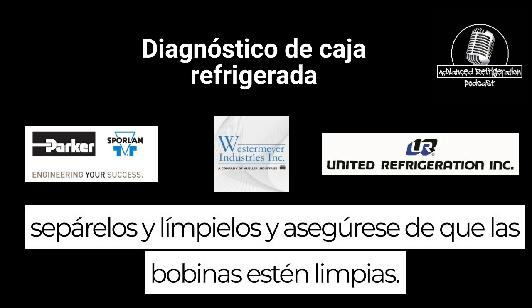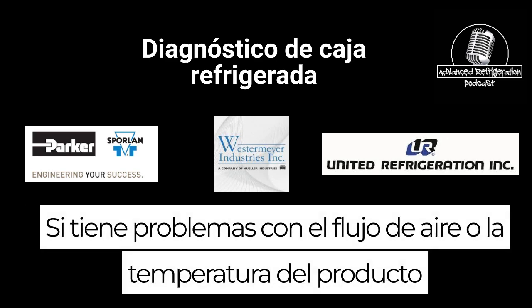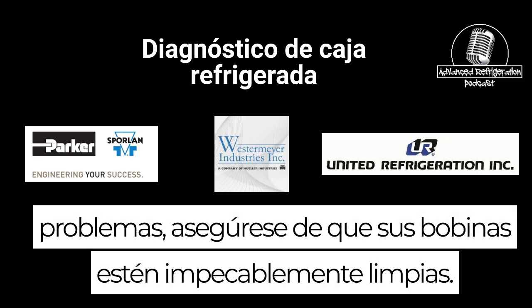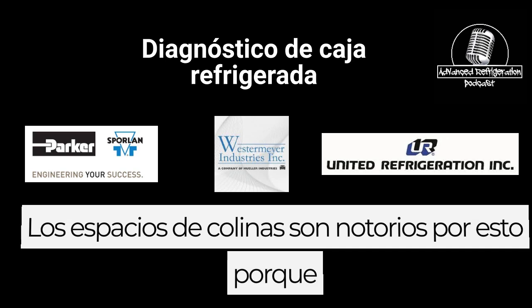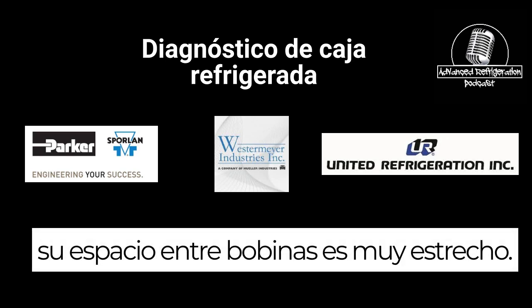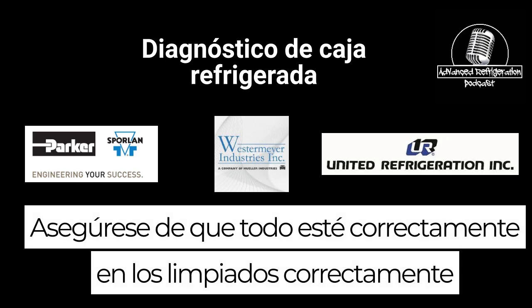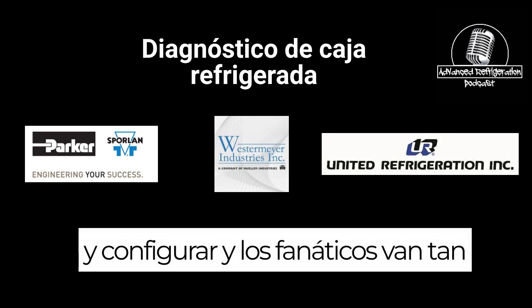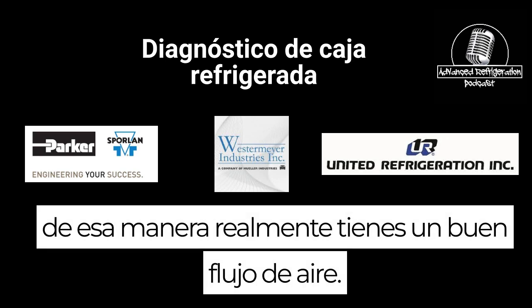Make sure the coils are clean. If you're having airflow issues or product temp issues, make sure your coils are spotless clean. Hill Phoenix cases are notorious for it because their coil spacing is so tight. Make sure that everything's properly cleaned and set up, and fans are all going, so that way you actually have good airflow.